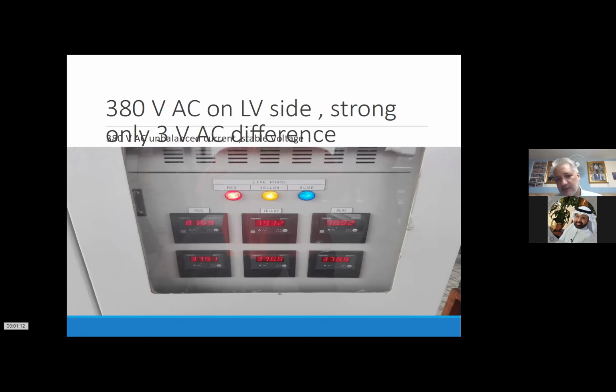In some instances, they cannot change it towards 400 volts, so you put it one step up, and check again if the stabilizing factor is now better, if we can inject more power, or if there are other issues arising. Normally, if it's a tight structure and within a 100-meter distance, it can easily be done.